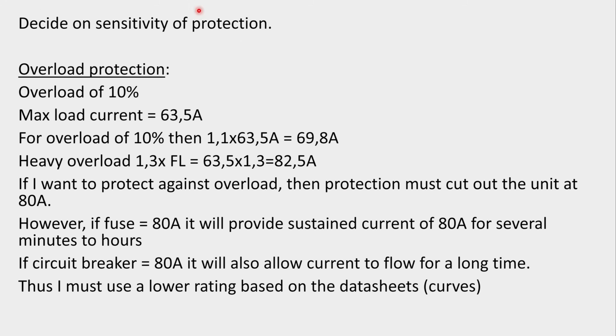Now I need to decide on the sensitivity of my protection. Let's look at an overload situation. Let's say the overload is only 10%. So that would mean the max load current would be 63.5 amps for 600 watts, but now increased by 10%. So 10% higher than 600 watts is now 660 watts. So the current for 600 watts was 63.5, but now it'll be 69.8 if the unit runs at a 10% overload.